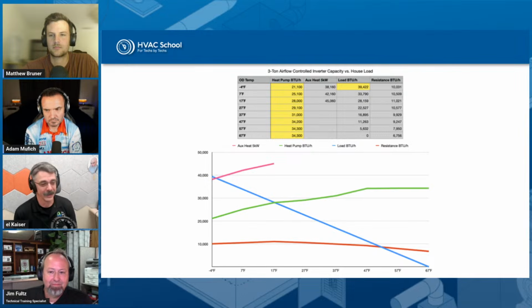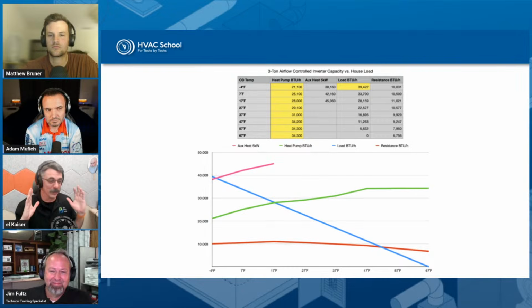One of the first, I'll never forget, one of the first geo or ground source systems I walked up on was in the summertime. It's a brand new unit, and the homeowner had hired their own well contractor for a closed loop system. They were complaining that it wasn't keeping up in the house. And I found that loop water temperature over 110 degrees. Wow. Return coming back. I called my boss because I'm green. I don't know hardly anything about this. And he's like, oh, that's not good. We're not going to be able to put any more heat into that yard.